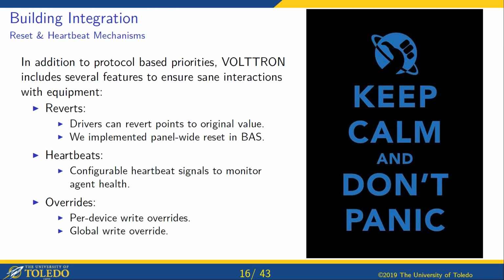But of course, we want to consider the cases where we don't want things to be left in a writable state. And VOLTTRON does actually integrate a fair number of facilities for making sure that communications stay sane and that we're not doing things which hamper the normal functioning of the building automation system. So whenever we have been writing to things, the drivers will automatically revert them to their original value. And VOLTTRON by default has heartbeats for letting the BAS know that things are operating. If they stopped, the BAS knows to take back control. And there are global overrides that can be set, which will force VOLTTRON to stop communicating with the BAS if control needs to be taken back at the building's level.